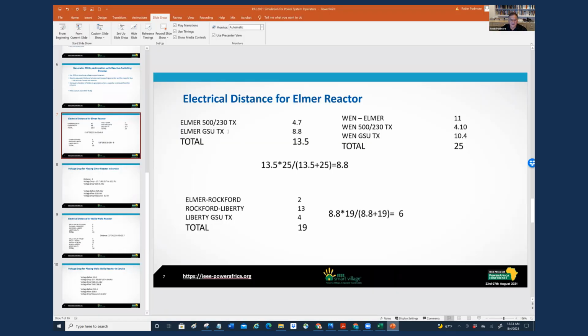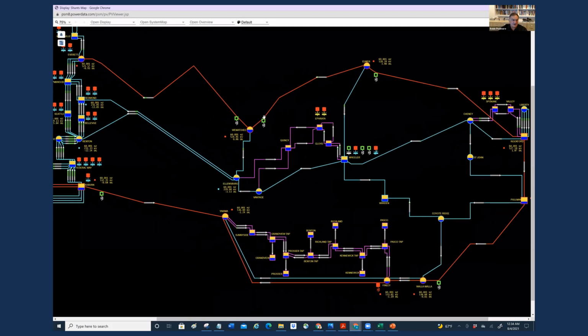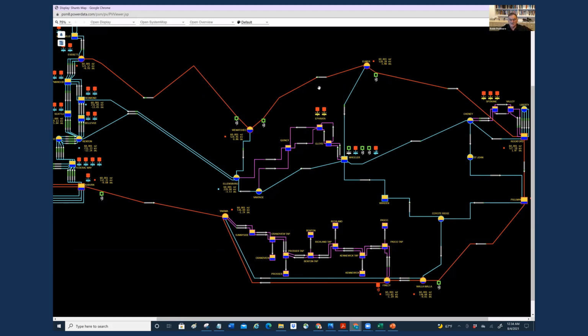So for Elmer, the number we get for the 2 500 to 230 kV transformers is 4.7 miles, and the number we get for the 5 step-up transformers is 8.8, giving a total of 13.5 miles. Now let's come over and look at the support we'll get from the Wenatchee generating station. Wenatchee is connected by this 500 kV transmission line, and that has an equivalent length of 11 miles.